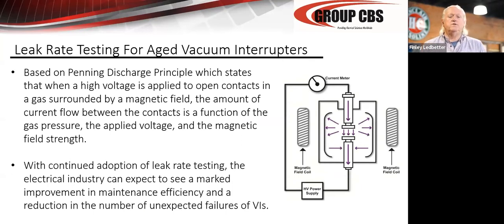Leak rate testing we can talk about. There are several manufacturers now building Penning-based leak rate detectors that can tell you the actual leak rate inside your vacuum interrupters and give you the actual pressure that's inside them. Really nice technology, really nice tool. Currently, this is in the NETA standards as an approved alternative to AC testing with the normal instruction book method. That particular test where you apply a potential is the acid test.